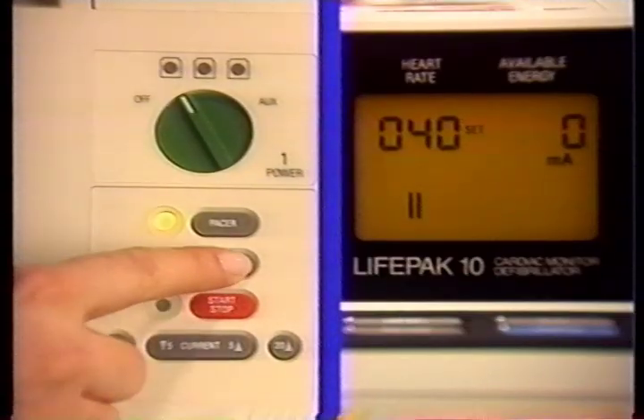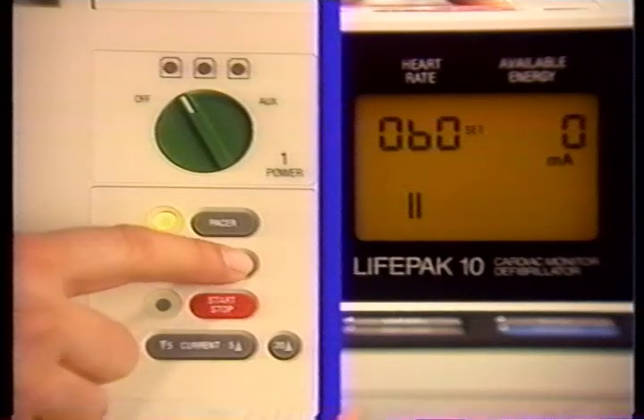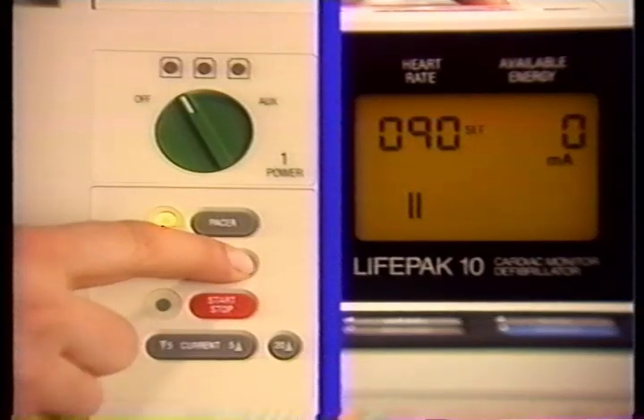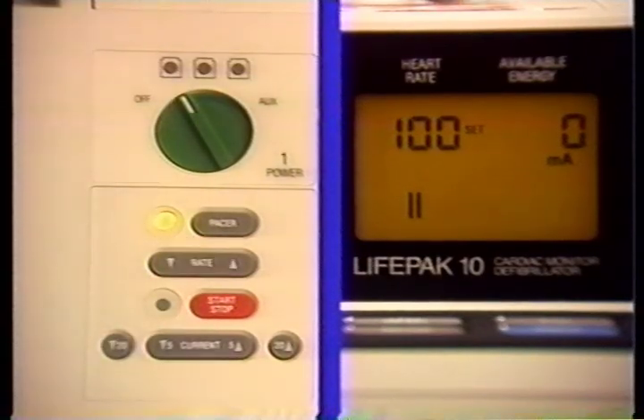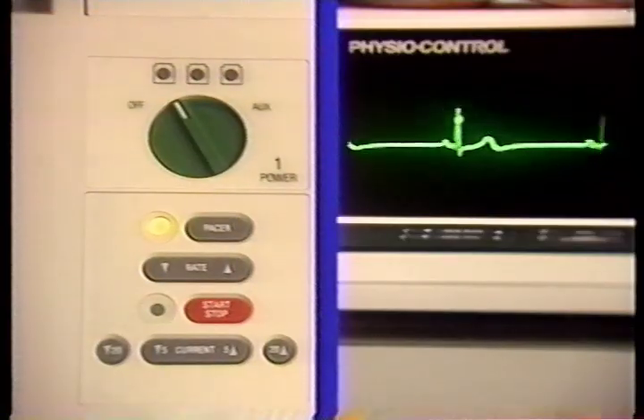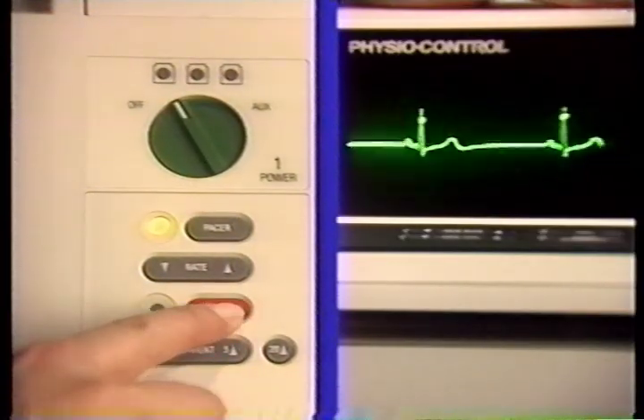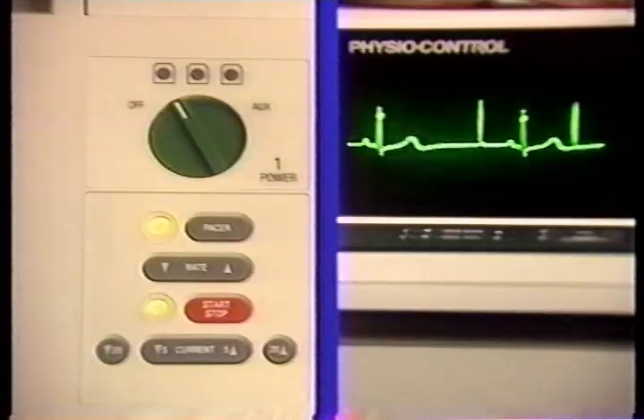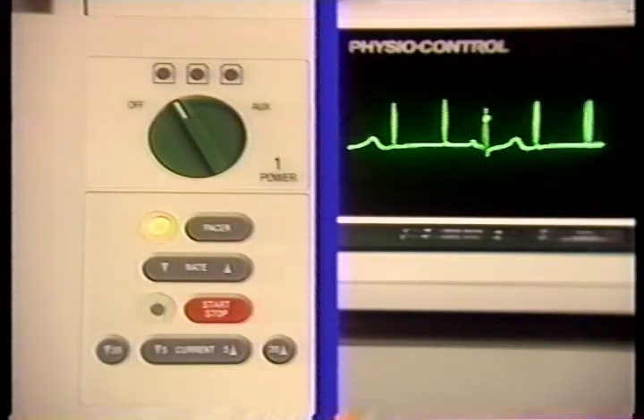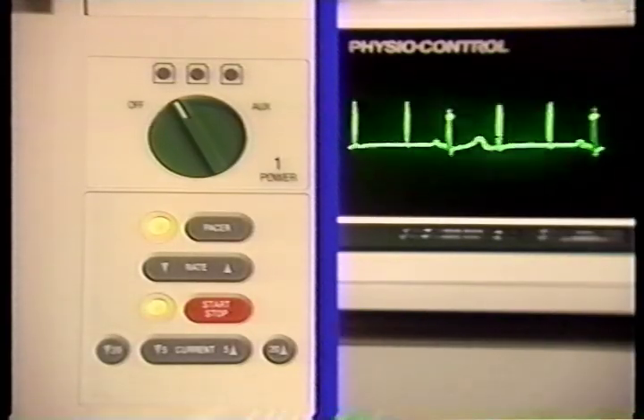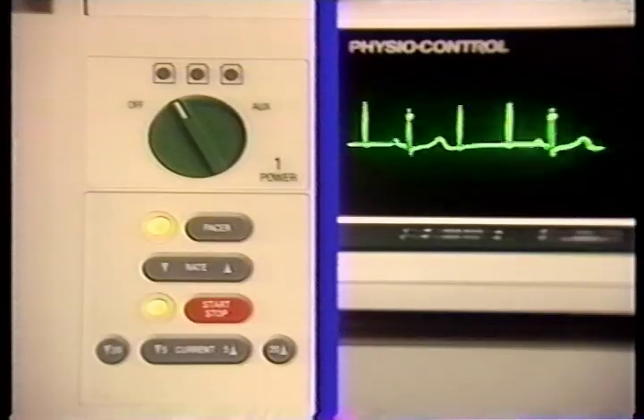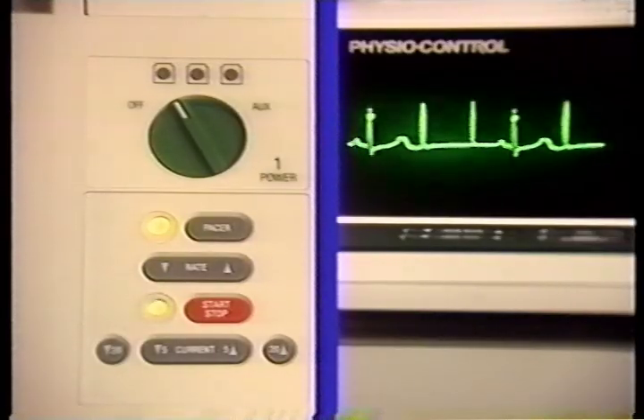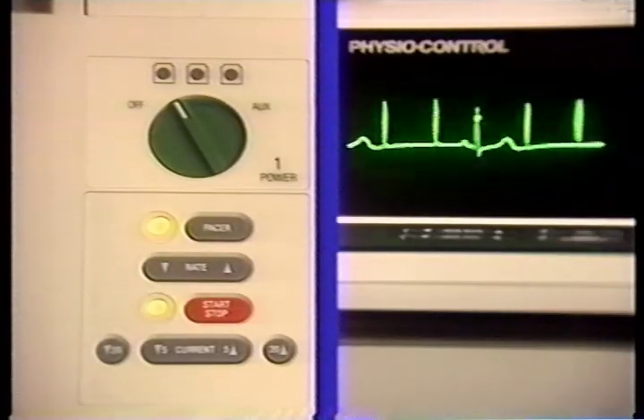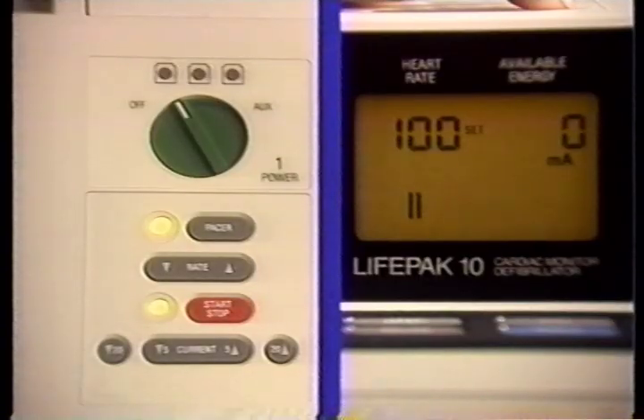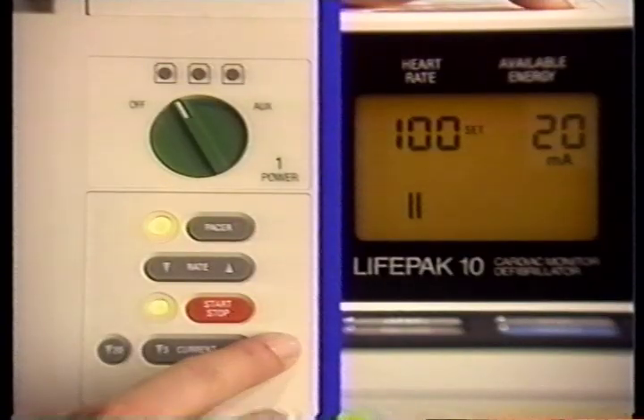Select the pacing rate from 40 to 170 beats per minute. Pushing the rate button will increase or decrease the rate in increments of 10. Push the start-stop button to begin pacing. The light to the left of the start-stop button will flash off with each pacing stimulus. An upright pace marker, or spike, will be seen on the ECG display with each pacing stimulus. Increase the current slowly in 5 or 20 milliamp increments while observing for capture.